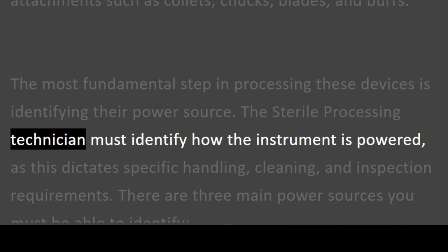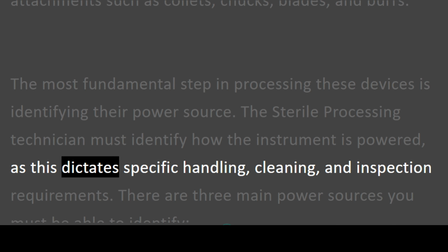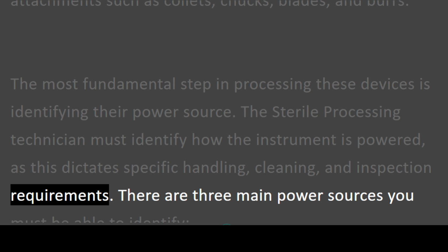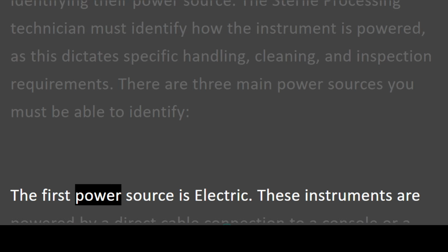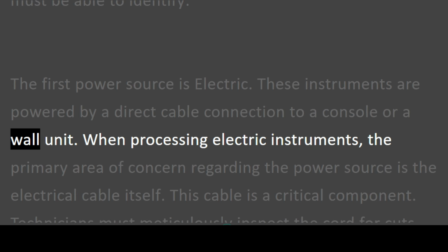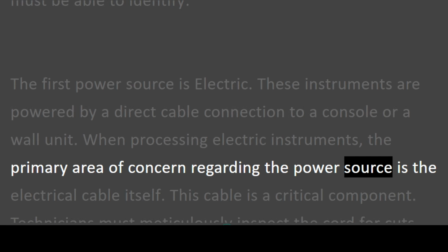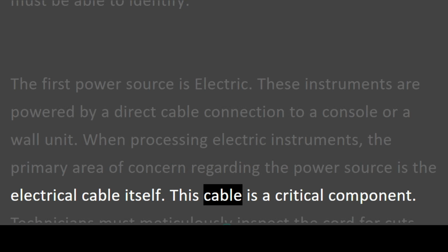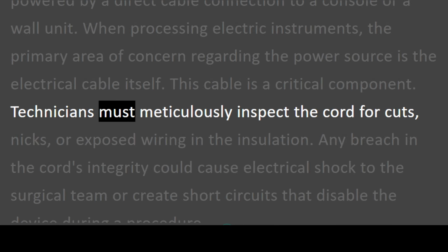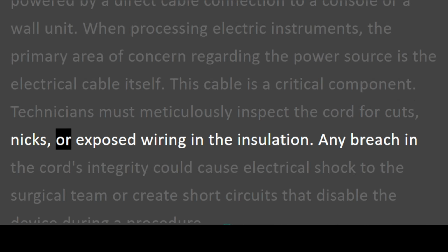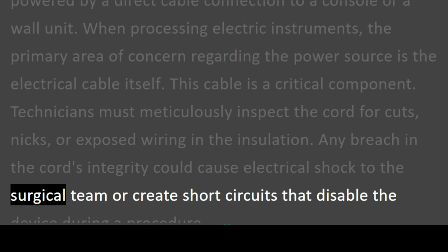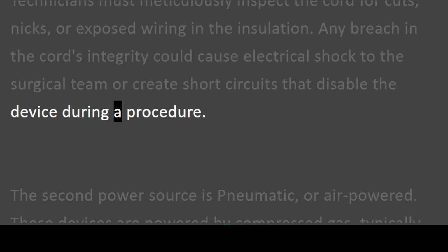The sterile processing technician must identify how the instrument is powered, as this dictates specific handling, cleaning, and inspection requirements. There are 3 main power sources you must be able to identify. The first power source is electric. These instruments are powered by a direct cable connection to a console or a wall unit. When processing electric instruments, the primary area of concern regarding the power source is the electrical cable itself. This cable is a critical component. Technicians must meticulously inspect the cord for cuts, nicks, or exposed wiring in the insulation. Any breach in the cord's integrity could cause electrical shock to the surgical team or create short circuits that disable the device during a procedure.